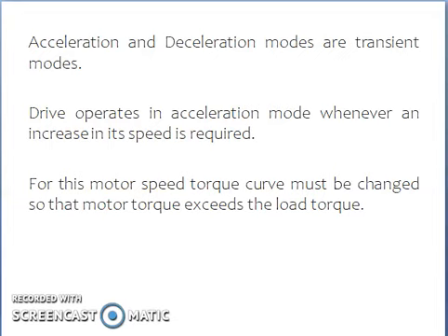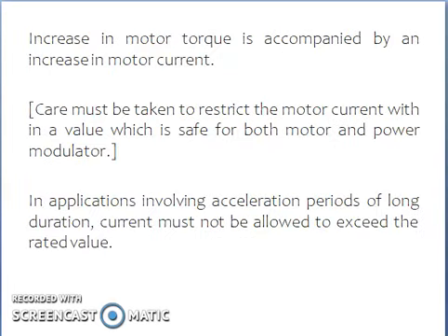An increase in motor torque is accompanied by an increase in motor current. So by just increasing the motor current, you can get more motor torque. But care must be taken to restrict the motor current within the safe values for the overall system, whether it is for the motor or for the electrical drive, say the power modulator.